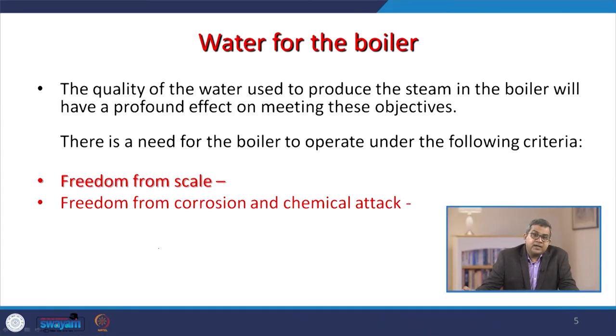The quality of water used to produce steam in the boiler has a profound effect on meeting the objectives of the boiler. There is a need for the boiler to operate under various criteria, including freedom from scale and freedom from corrosion and chemical attack. We discussed previously how scales are generated and how dangerous they are. Apart from scale, corrosion and chemical attack are also important because debris may carry metal particles, and if steam is used directly in any chemical reaction, it may create a catalytic effect.